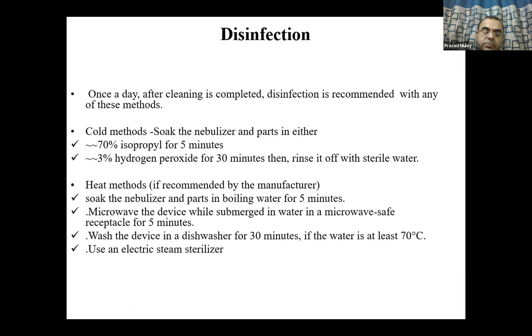And the heat method, if it is recommended by the manufacturer, since sometimes it may damage the device. So if it is recommended, then you can soak the nebulizer and parts in boiling water for 5 minutes, or microwave the device while submerged in water in a microwave safe receptacle for 5 minutes. Wash the device in a dishwasher for 30 minutes, with water at least 70 degrees. There are different varieties, mechanisms by which you can do it, and you can use an electric steam sterilizer. So there are different varieties by which you can do the heat methods.